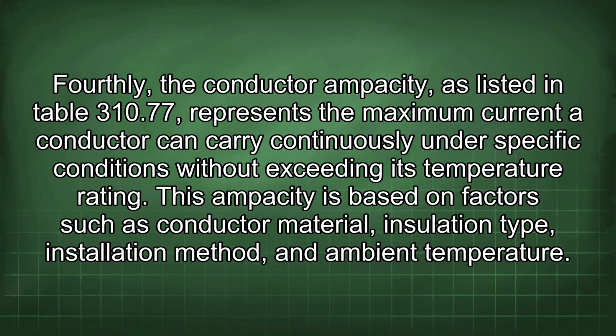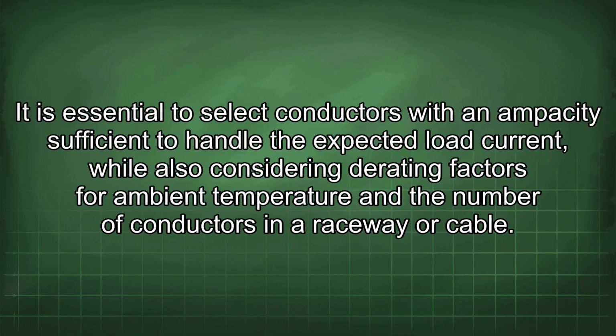Fourthly, the conductor ampacity, as listed in Table 310.77, represents the maximum current a conductor can carry continuously under specific conditions without exceeding its temperature rating. This ampacity is based on factors such as conductor material, insulation type, installation method, and ambient temperature. It is essential to select conductors with an ampacity sufficient to handle the expected load current, while also considering derating factors for ambient temperature and the number of conductors in a raceway or cable.